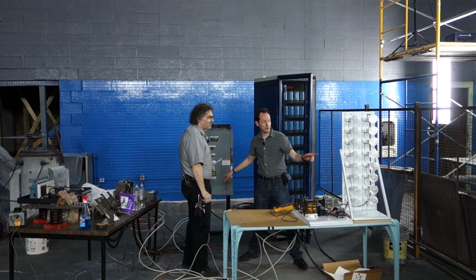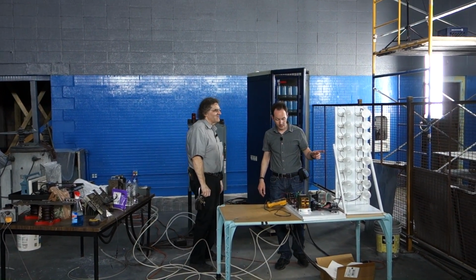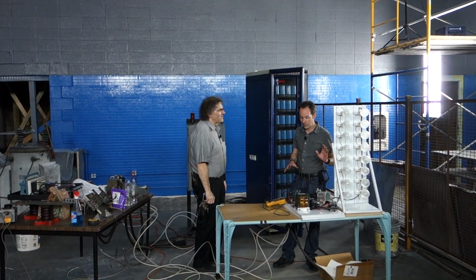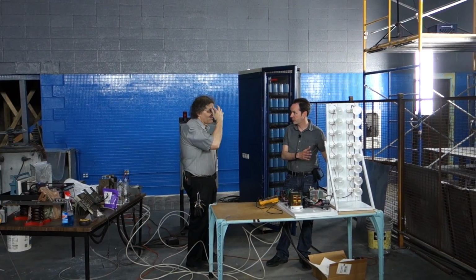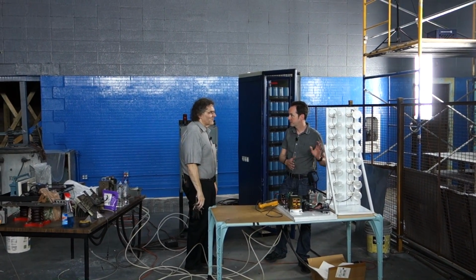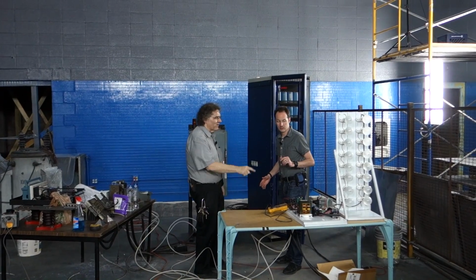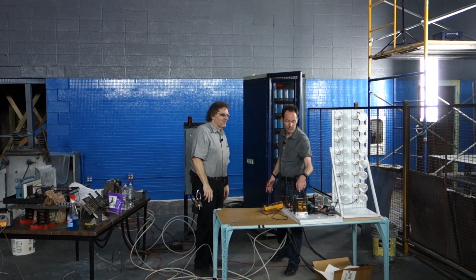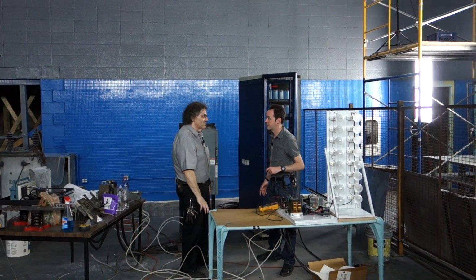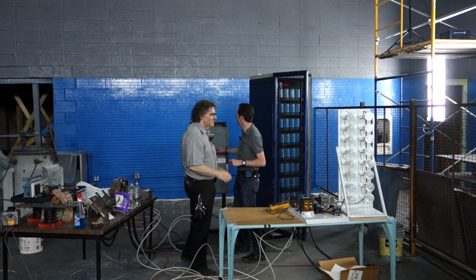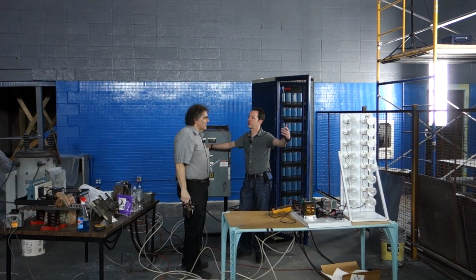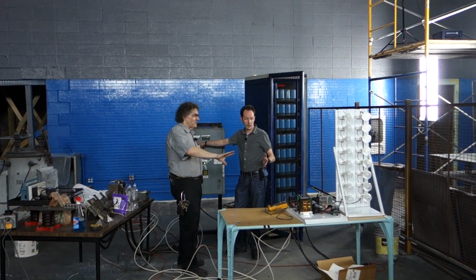Here it's continuous, and that means we've got like 4,000 volts going into the lights - 2400, very accurate measure, 20 to 1 transformer. It's a voltage doubler circuit, so they're 4,000 volts. We took measurements, we made sure.